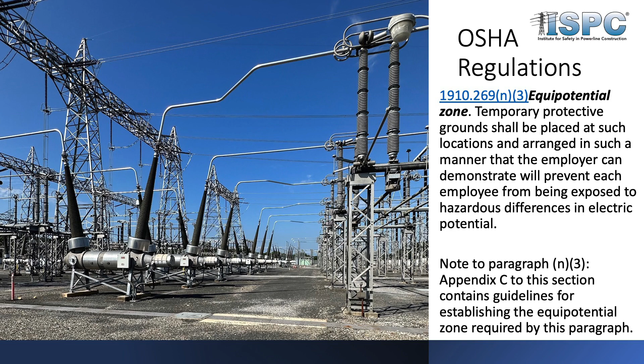Equipotential zones, work zones, apply to substations just as they do to the T&D world. If you look at OSHA, all the examples are around poles and structures — there are no examples in OSHA's regulations around substations and equipotentially grounding and bonding in substations, but it applies all the same. Especially as you get up in voltage levels — 230 kV, 500, 765, and so on — the induced voltage possibilities in those scenarios are so great that we need to be equipotentially grounding and bonding ourselves into our protected work zone. If we're not, it's only going to be a matter of time before you become one of those statistics.